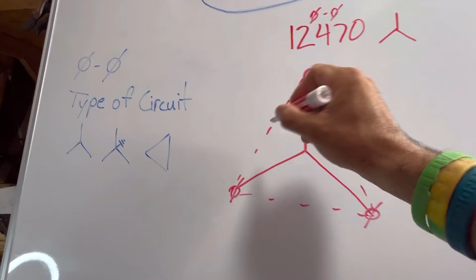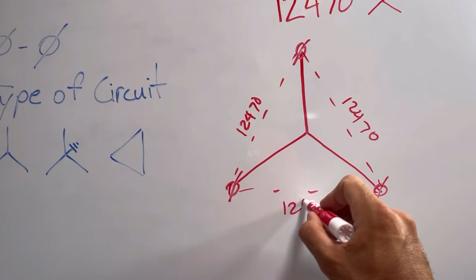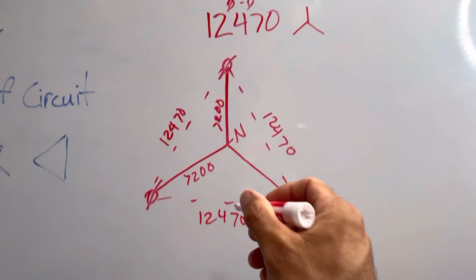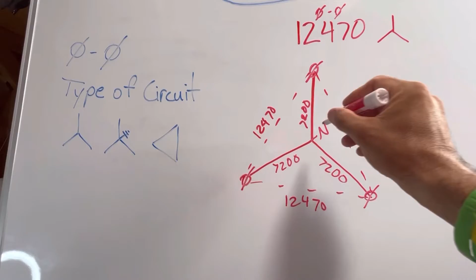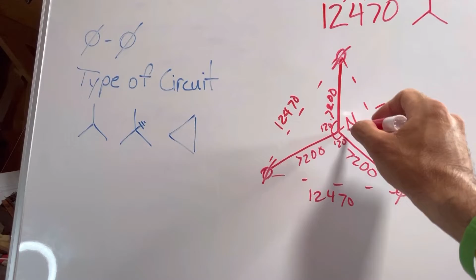So what we're looking at here are two different voltages to work with, right? We've got 12,470 phase to phase, and then phase to neutral, we've got 7,200. And guys, in a later video, we're going to break down exactly how you figure all this stuff out and why these voltages are what they are. There's a really easy mathematical formula that we use to explain all of this, but it really just comes down to angles and distance. If I had a 7,200 inch line, a 7,200 inch line, and a 7,200 inch line, and they were in this configuration or a Y configuration, separated by 120 degrees, right? So 120 degrees, 120 degree angle, 120 degree angle right here.